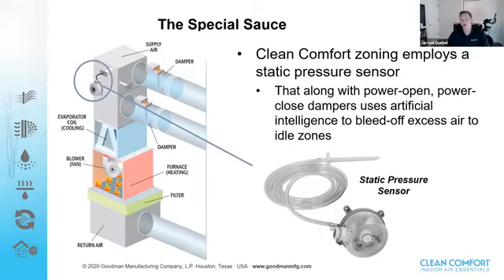Well, first of all, that's not very efficient. We're taking air that we've already conditioned and then we're reconditioning it. And when we start to actually bypass too much air, not only is it not efficient, but we can run into issues where we're freezing up coils, tripping limits, and in extreme situations, even cracking heat exchangers. So our ESP system completely eliminates the need for bypass. Furthermore, it's a great value to the contractors, and any of you out there watching this presentation that have had the experience of installing a traditional bypass, I'm sure you're nodding your head and saying that anytime you don't have to do that, it's a good day.